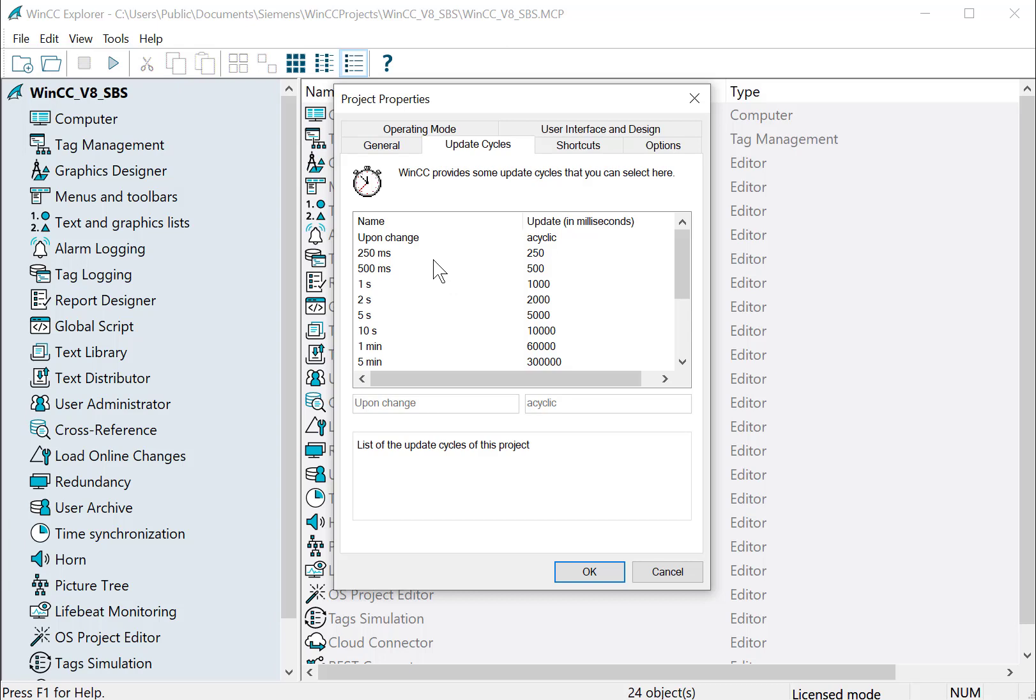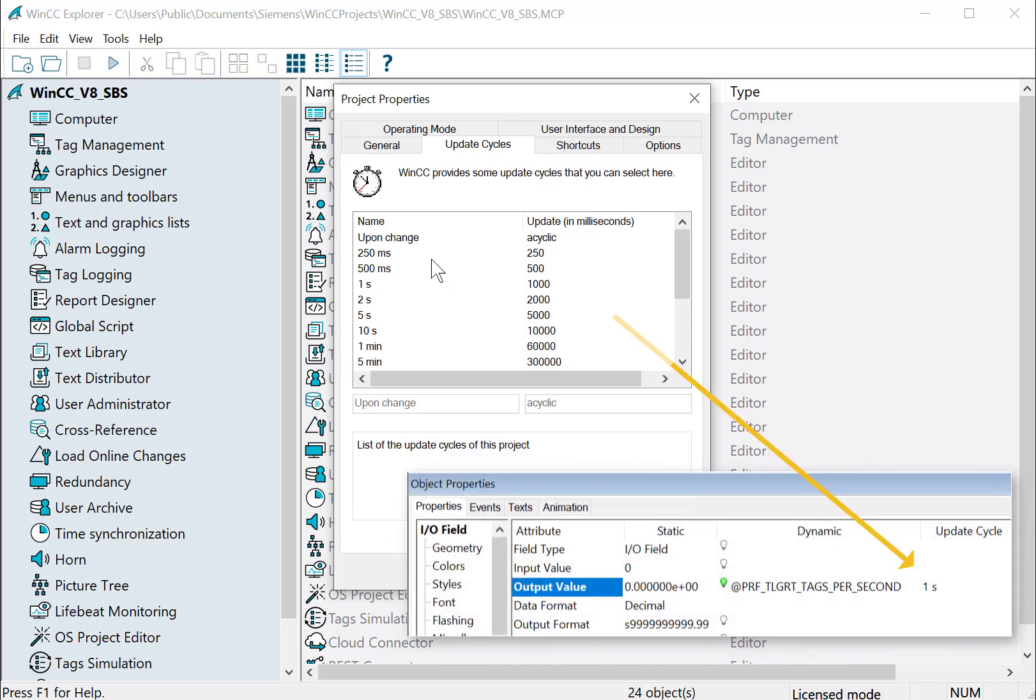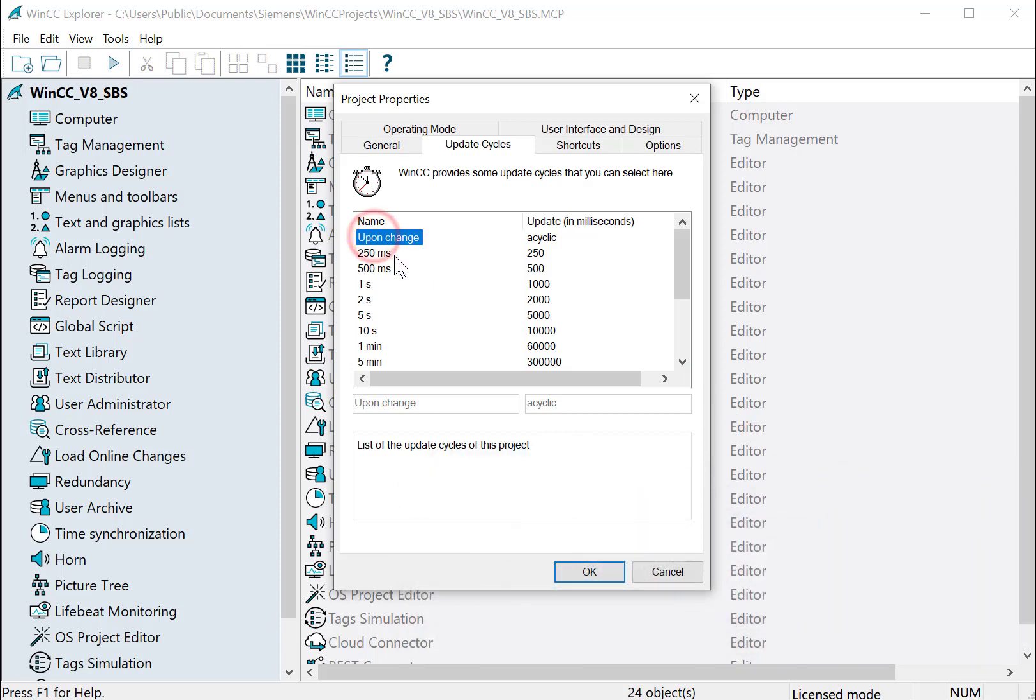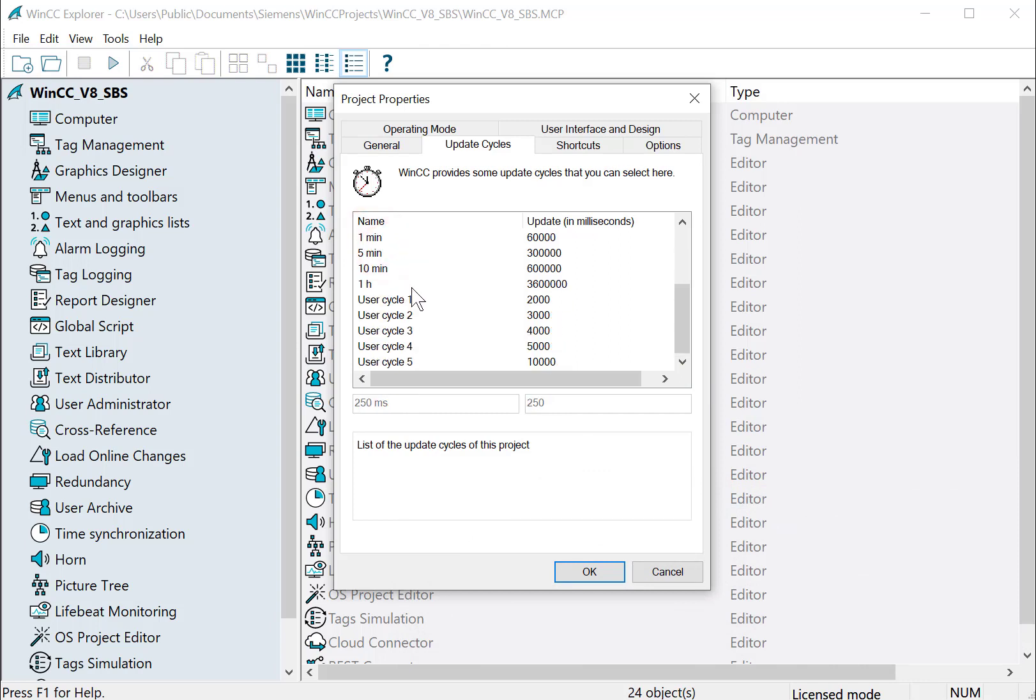In WinCC, the update cycle is not a property of the tag. It's a property of a tag connection to a graphic object or something. And they have all the time cycles you might expect. There's also an upon change, which is good to use.